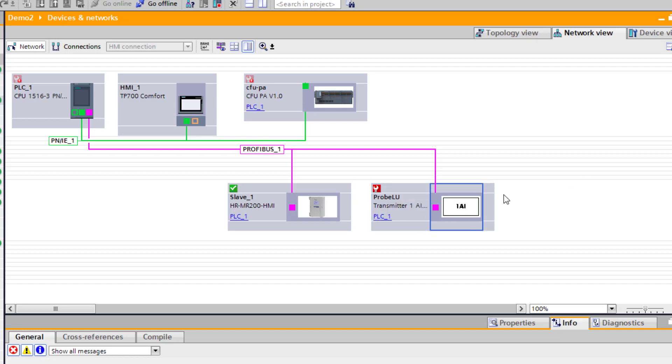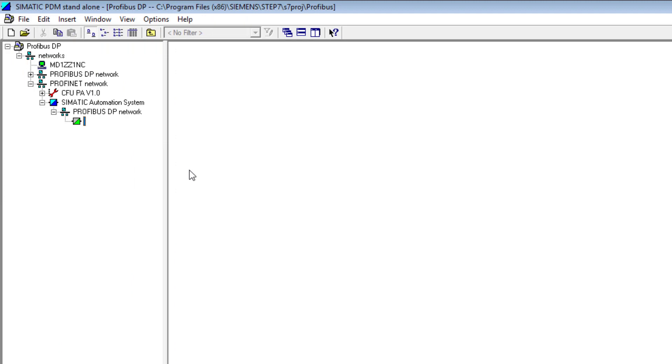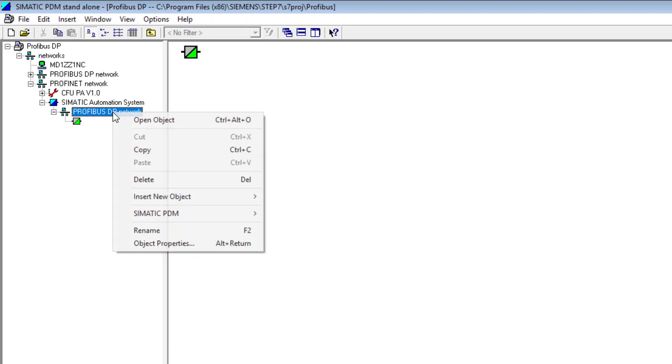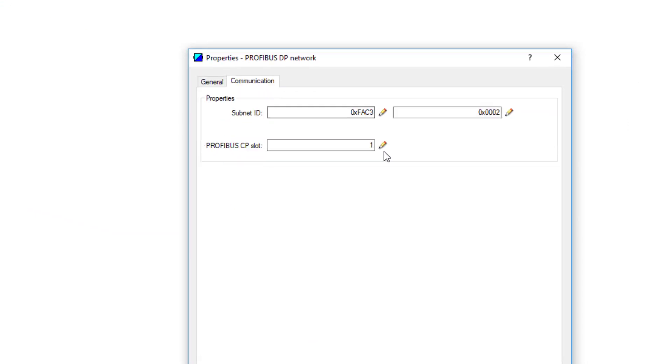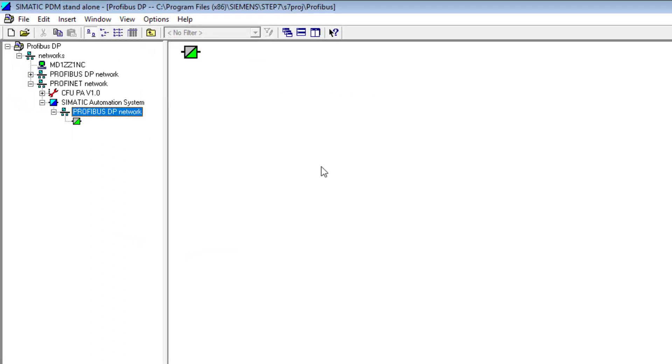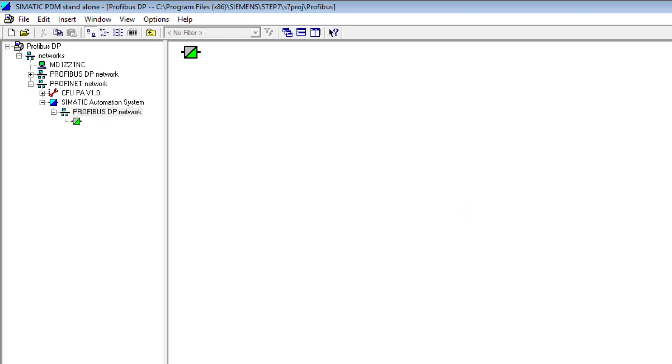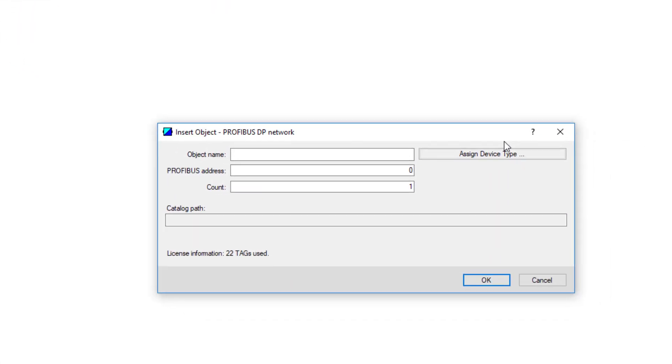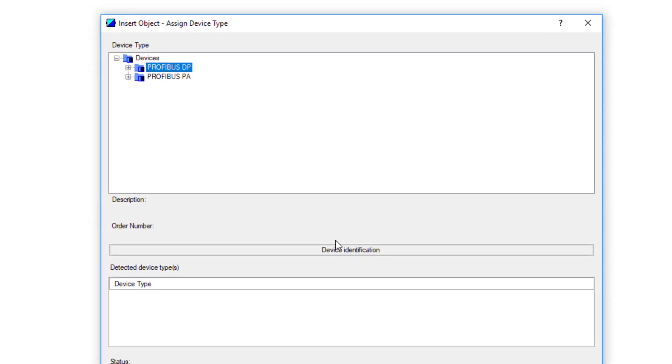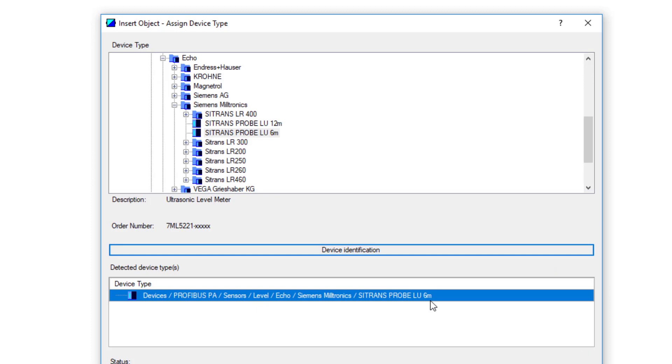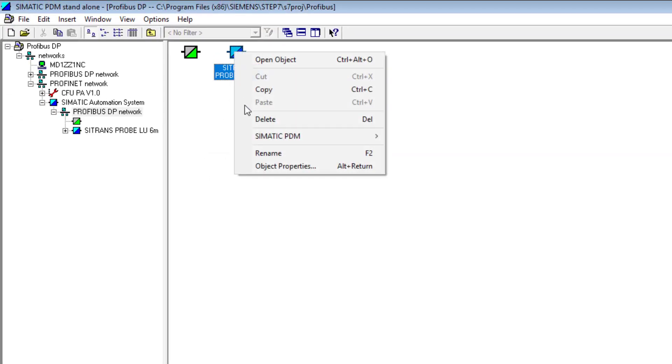Here we have our existing PDM projects that we've been working on before. You can remember we had to set subnet ID, so this was already communicating to our hydro 200. So in here, insert new object, and it shouldn't matter that we're using a generic GSD. What you'll see is when we're using the device identification, it will try and pull in a generic EDD, but you can force it to use the manufacturer specific EDD. It's found it anyway, so there we go. See my project.